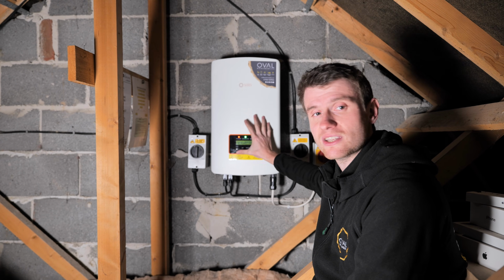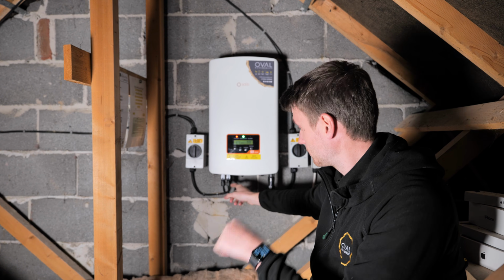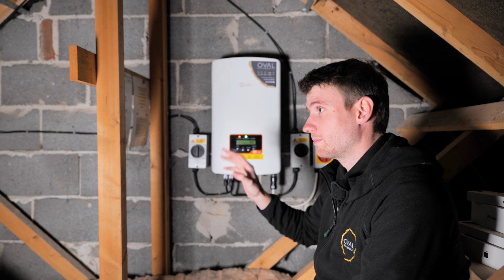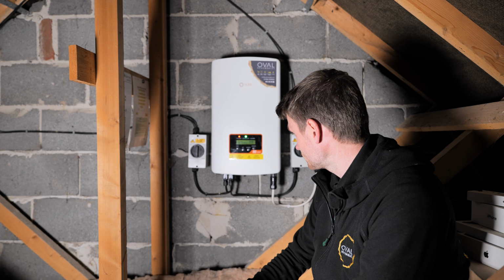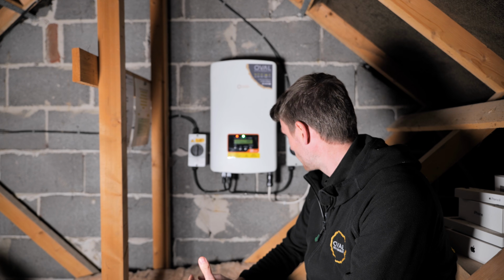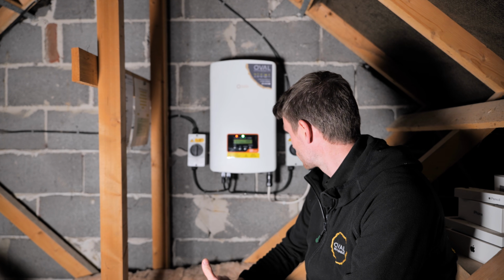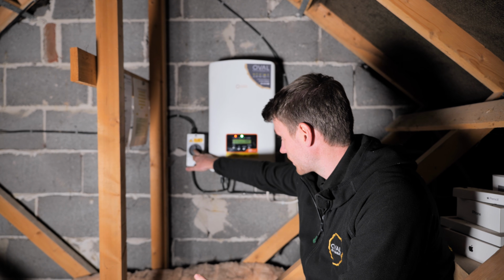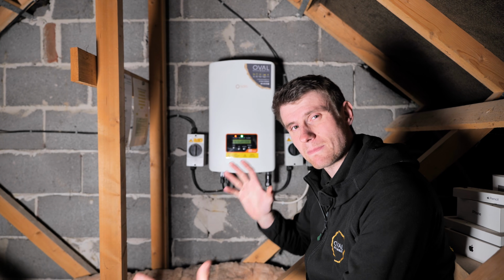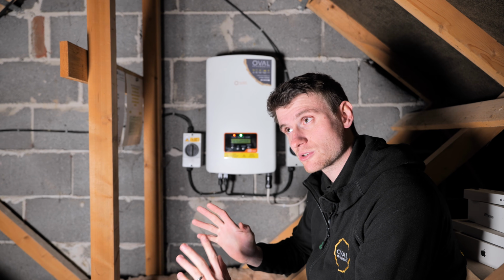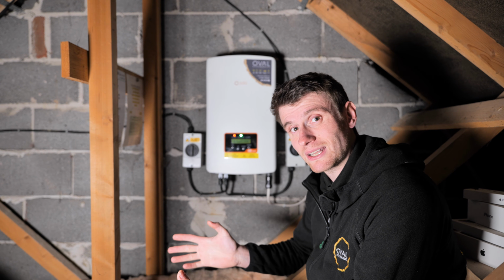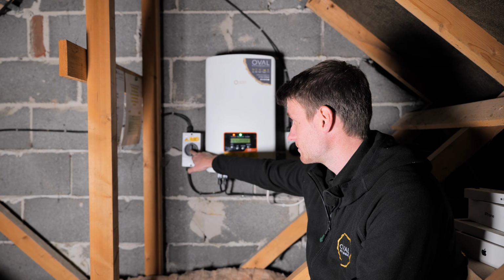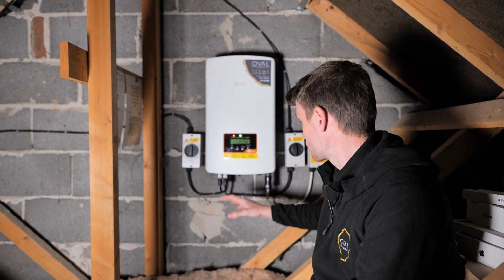As part of this, we did a full test on the solar PV just to make sure the panels seem to be working okay. There didn't seem to be any faults on any of the strings. So we've got a string here and a string there - that's basically a bank of panels. I can't remember exactly how they're split up, but we've got 16 panels out there, so let's imagine 8 panels and 8 panels on each of those strings.